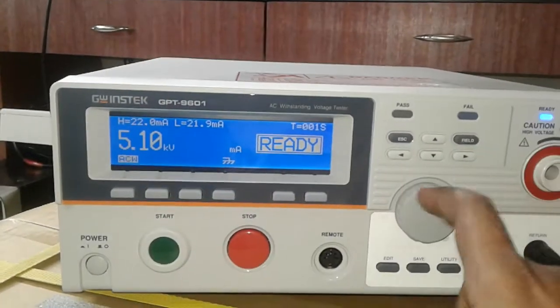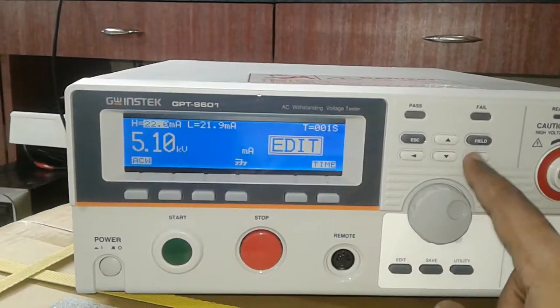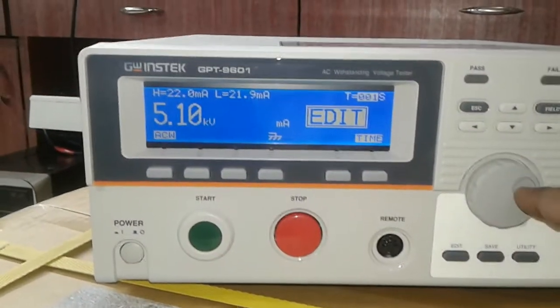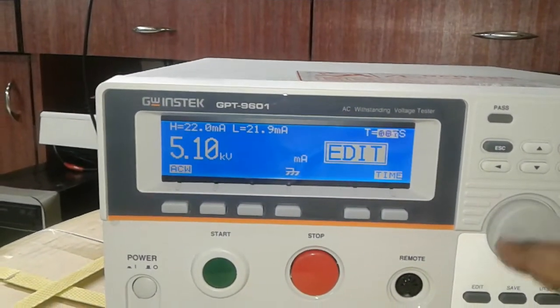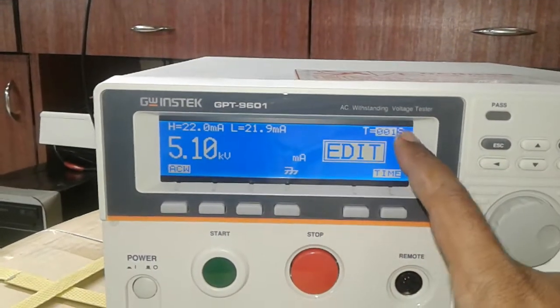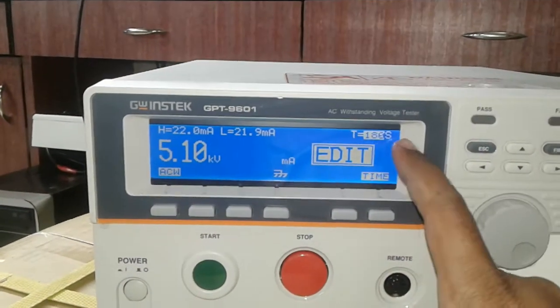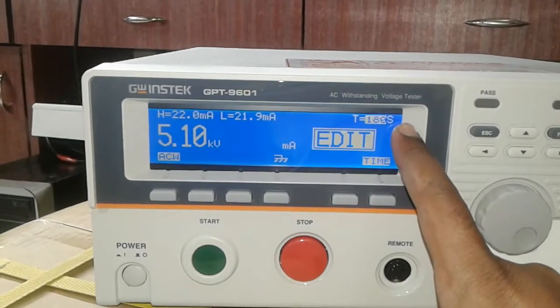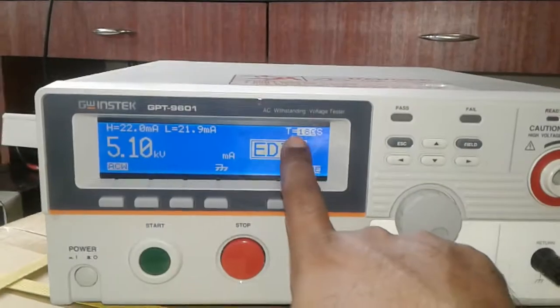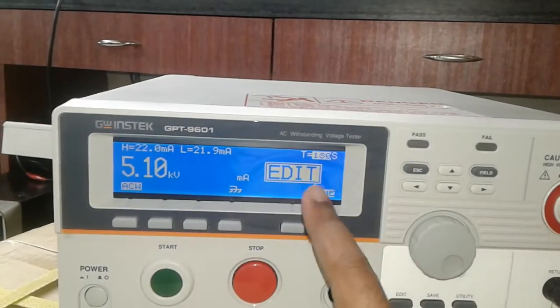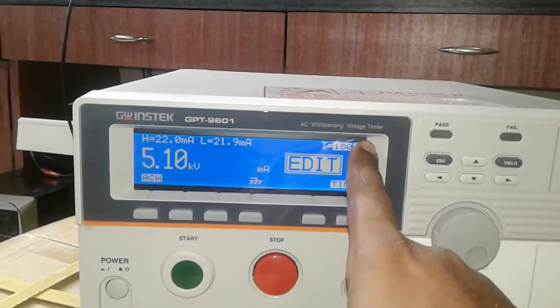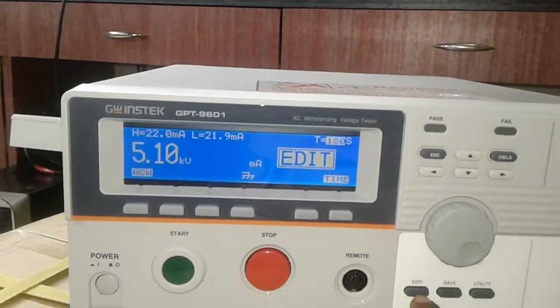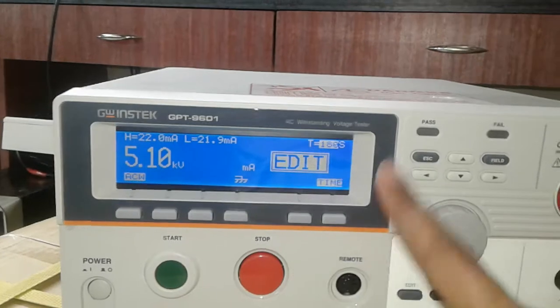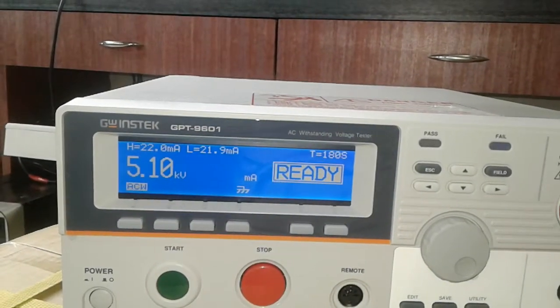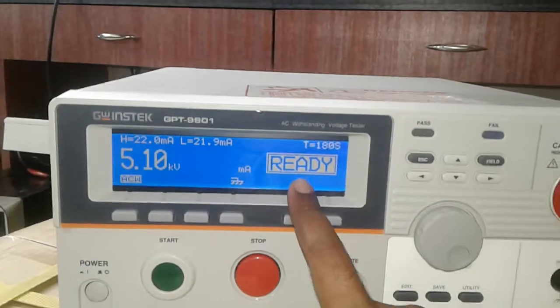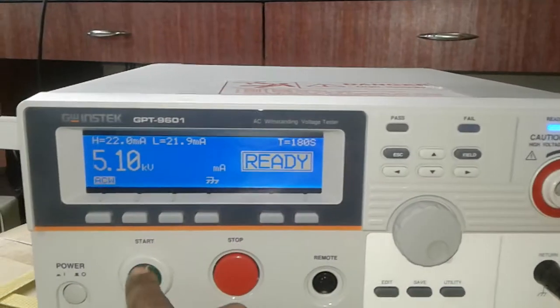If you want to set the test time, okay, from here you can set the test time. Minimum 1 second, maximum 180 seconds you can set from here. Okay, this is actually the test time. Editing the high limit, low limit, and test time will be possible when you press this edit button. Okay, after the edit you have to save the setup. Then when the ready indicator lights up here, along with this light, you can start the test.